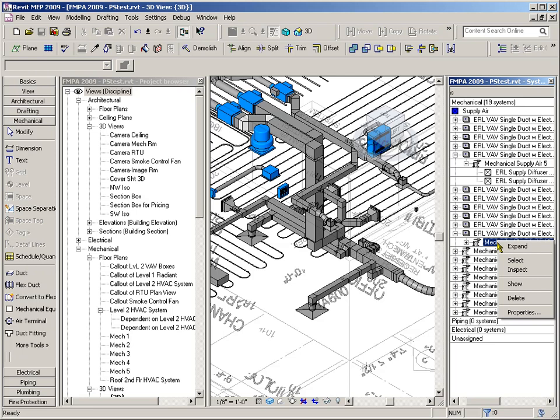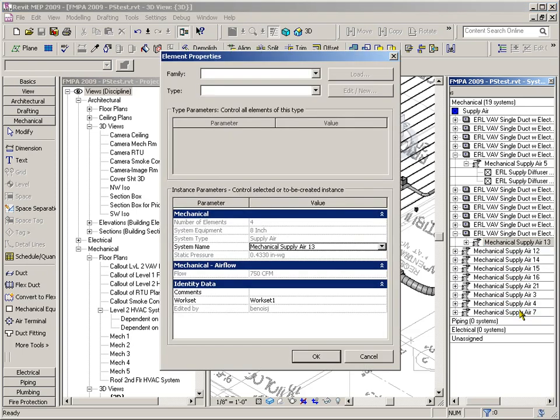And if I right-click on this and go to Properties, it is correctly calculating that static pressure. So we've now fixed Supply Air 13 logical system. It is now a complete system. All the diffusers are grouped into the logical system. And we've specified the equipment to be in the logical system. And the connectors are all correct.